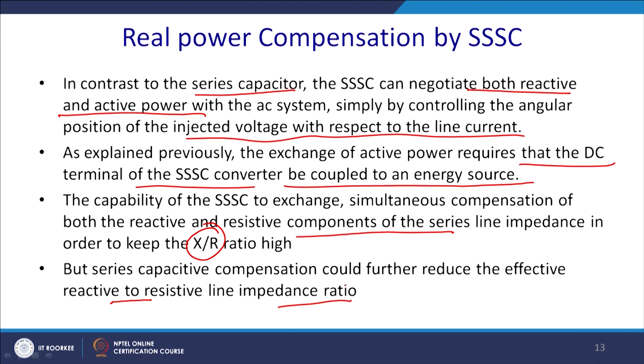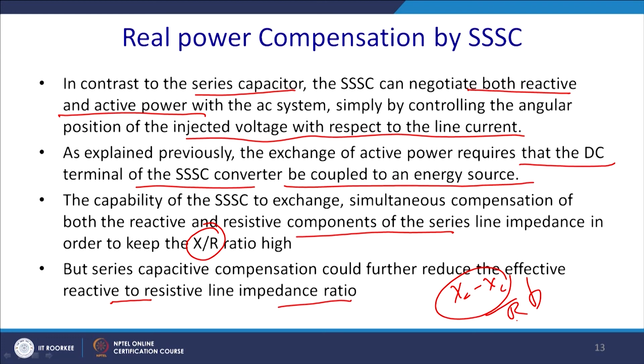But series capacitor compensation would further reduce the effective X by R ratio of the line impedance. That is one of its problems, because it becomes XL minus XC. So, this ratio X by R gets decreased, but in this case it is possible to maintain the X by R ratio. Then what happens? The line impedance ratio progressively decreasing increases the reactive power demand of the line and the associated line losses, and the possible voltage depression would start to limit the transmittable real power. So, voltage sag and others. For the normal range of control, the uncompensated X by R ratio of the line is chosen to be 7.4. That is what I was saying, that in the previous slide this ratio is around 7.